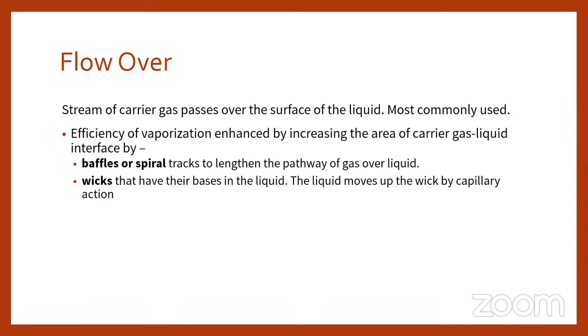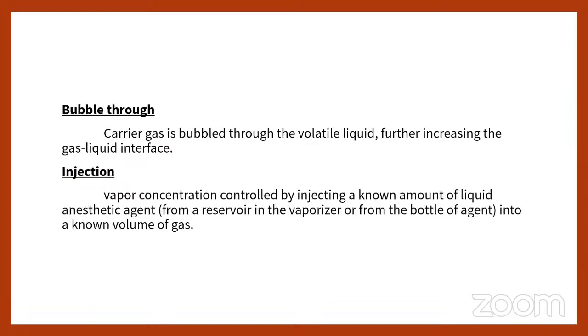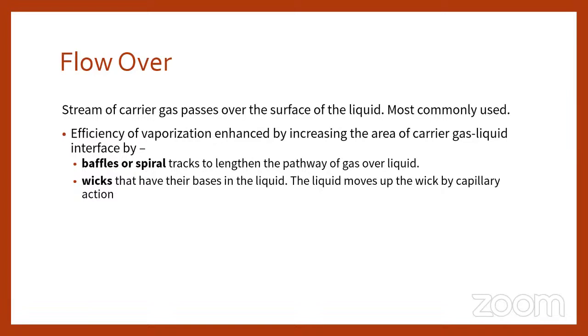Depending on the type of vaporization, there are three types: flow over, bubble through, and injection. Flow over is basically a stream of carrier gas passing over the surface of the liquid. It is most commonly used. The efficiency of evaporation increases with increasing the surface area of the gas and liquid interface. To increase the surface area, we have several tricks up our sleeves. Basically, we incorporate wicks and baffles in the vaporizer system.